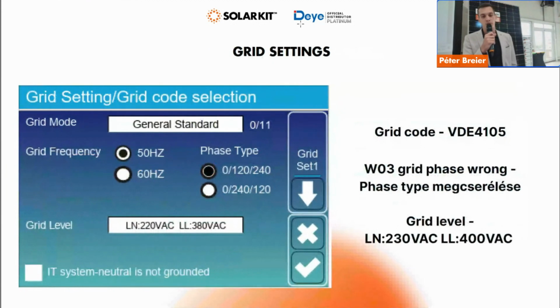Usually we use VDE 4105 grid code. This is the general one for Germany, for Austria, I believe as well. We used it in Hungary. I'm not that familiar with all of the grid codes around Europe, but I think this can be used by most of the countries. And we have 50 Hertz connection. Also, you can rotate the phase order with the phase type settings. You don't need to physically change the phases.